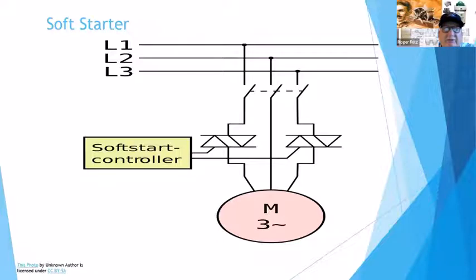Then actually came out from NASA, there was a NOLA device created, which was basically just taking, instead of having the power lines coming directly in through a starter to the motor, they used SCRs or triacs in here to basically be the power source to the motor. The advantage of that was you were able to ramp the voltage and frequency up. The disadvantage is you weren't able to really change the load on the motor wherever it was. So it was kind of a fixed speed again, catching up with those 60 hertz power, or in Europe, 50 hertz power, 380 volt.